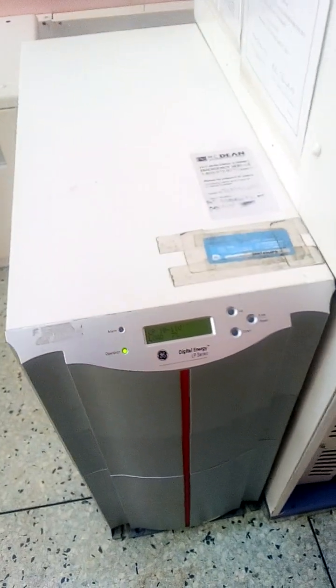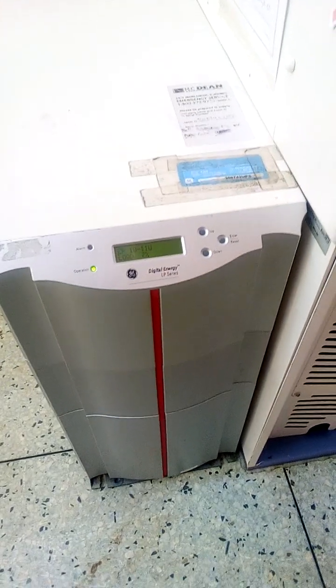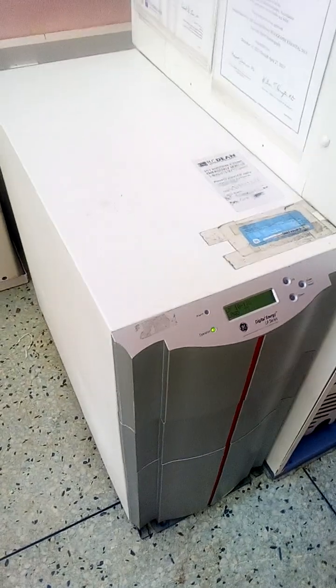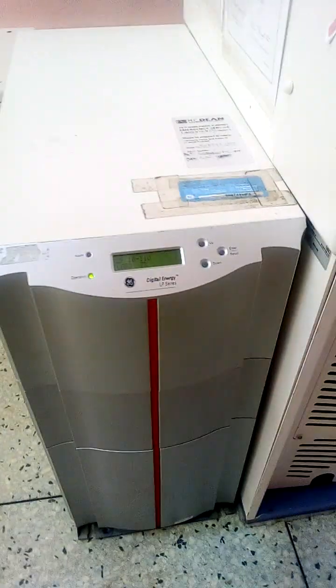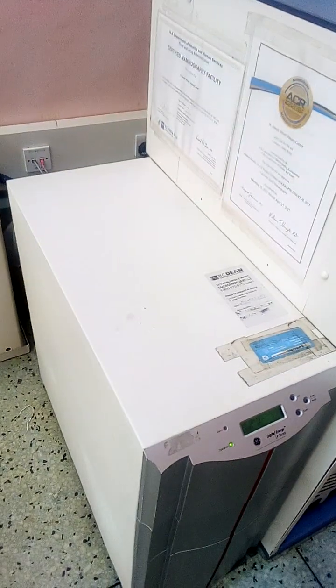And also once the images have been taken, they will also be displayed on the screen. Now down here you have the generator. This high voltage generator for the mammo is placed strategically down there, and then if you come over, you can also see we have the UPS. The UPS is responsible for standby power. If the power fails from the utility, this UPS will take over and supply power to the mammo unit. So it's a big one. As you can see, it's a big UPS.